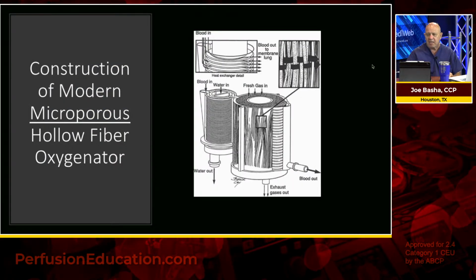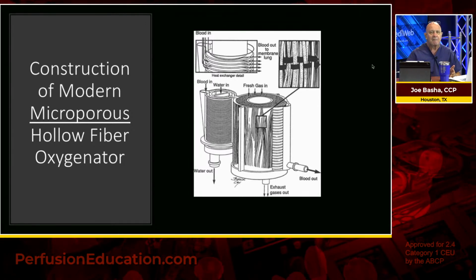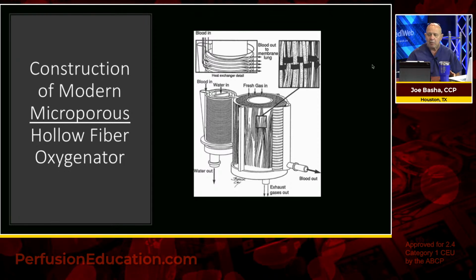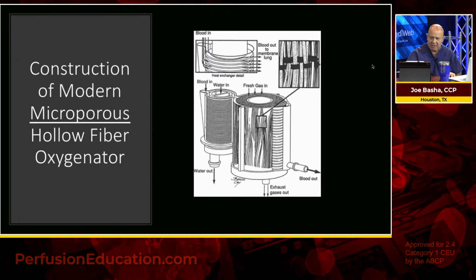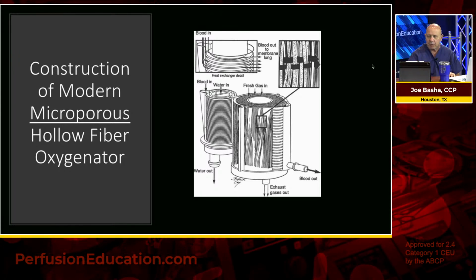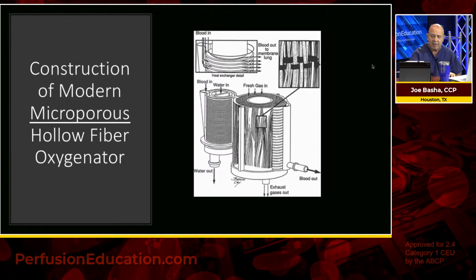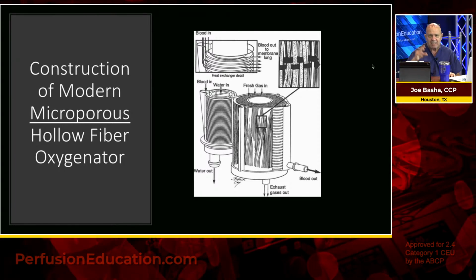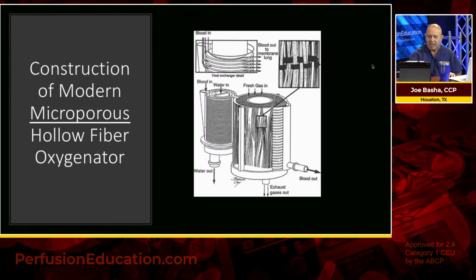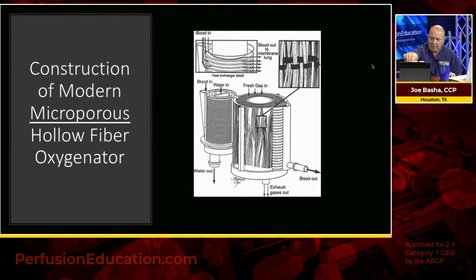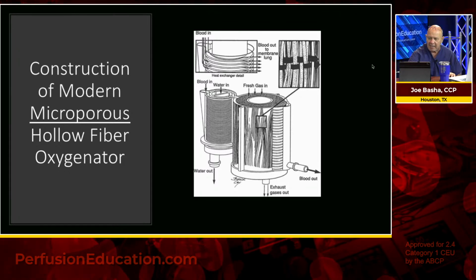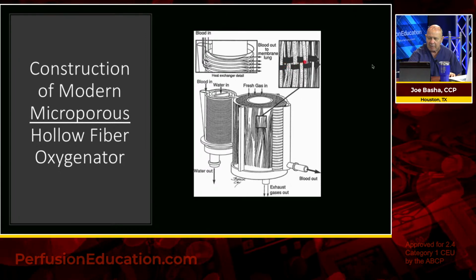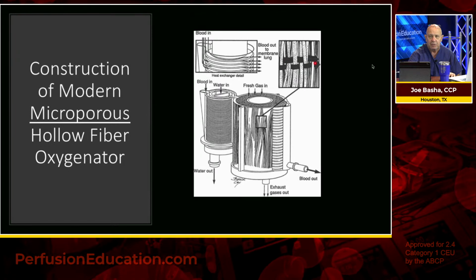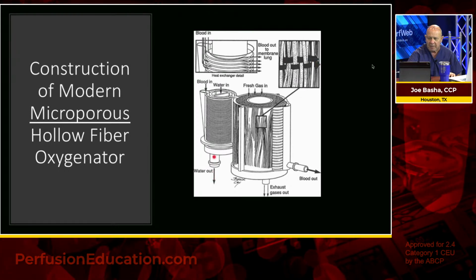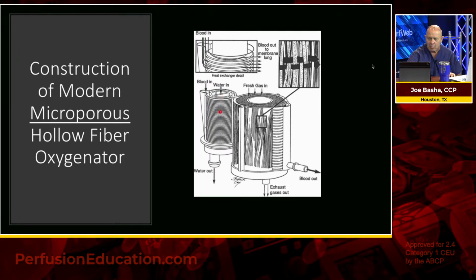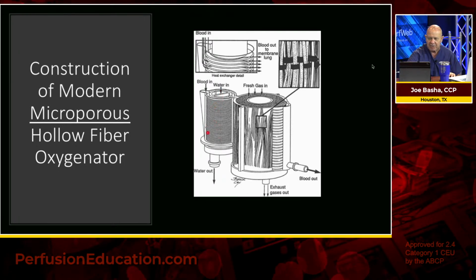Polish connection. Okay, so let's discuss the construction of modern microporous hollow fiber oxygenators, and that's what you see in this picture here on the right. You have your heat exchanger. It's not integrated, it's separate. There's been several different designs of these things over time, and this is probably a pretty old picture. But if you look up here, in the top right, this arrow represents the blood flow passing through the fiber bundle. So you have your water in up here, you have your water out down here. This is your heat exchanger, stainless steel.